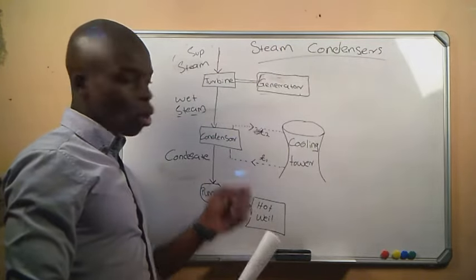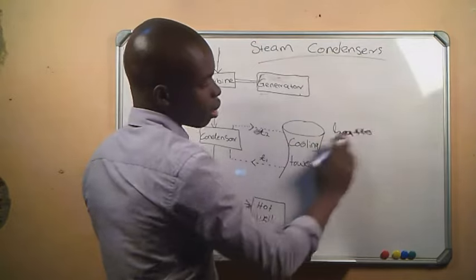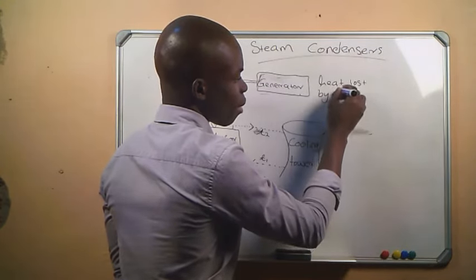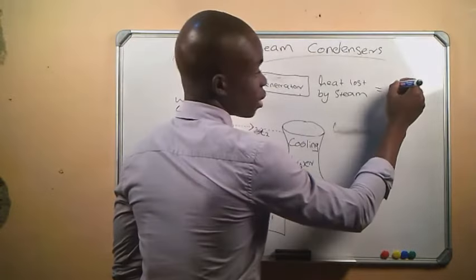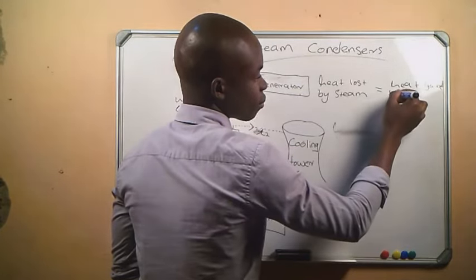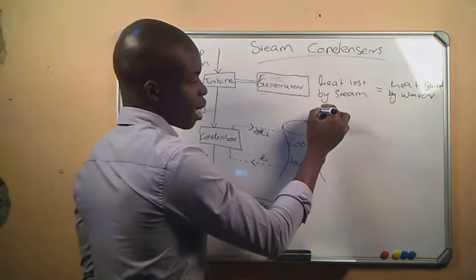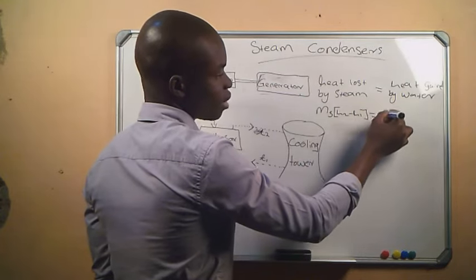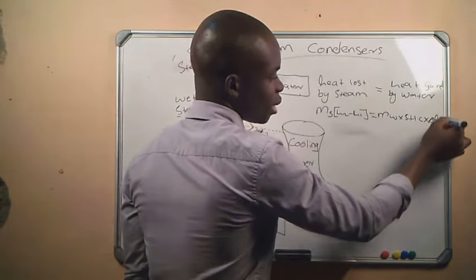Between the steam and the cooling water from the cooling tower, the heat lost by the steam equals the heat gained by the cooling water. This gives us the formula: mass of steam × (h2 − h1) = mass of water × specific heat capacity × change in temperature.